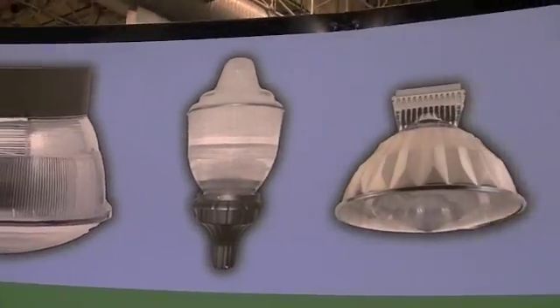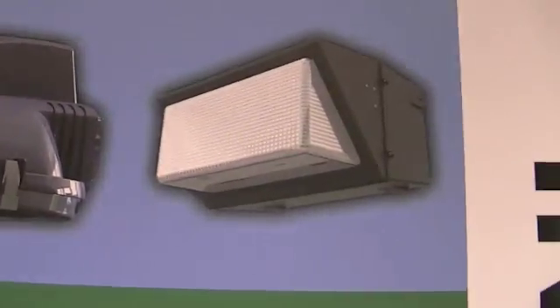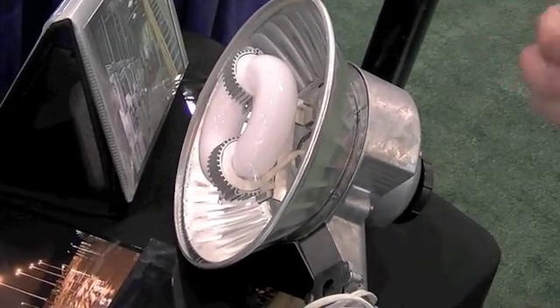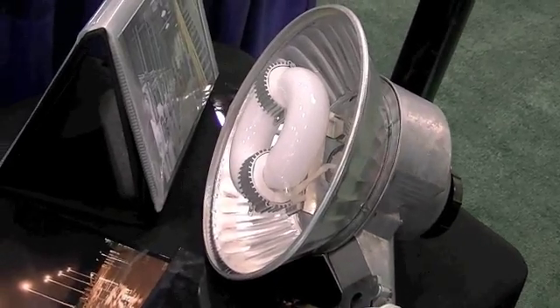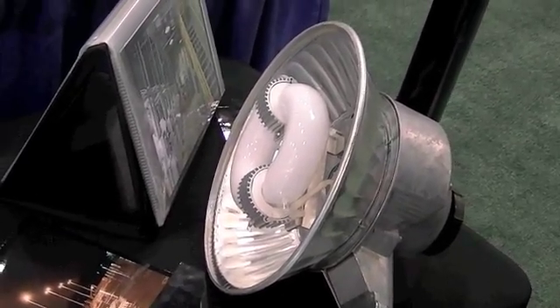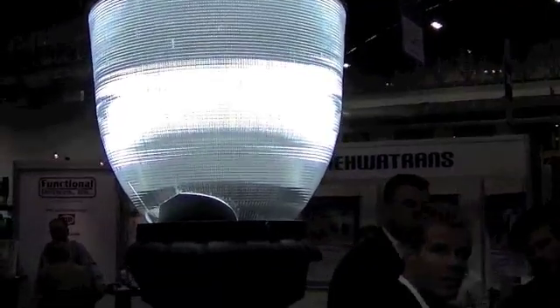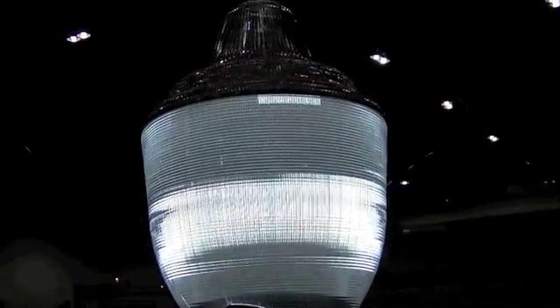Here's another type of outdoor lighting fixture — induction lighting. It looks like fluorescent, but it's also referred to as the electrode-less lamp. Like fluorescent lights, those have little electrodes that spark to ignite the gases. Here, you don't have electrodes, so you don't have anything to spark — no sparking, no noise. That basically means nothing to wear out.